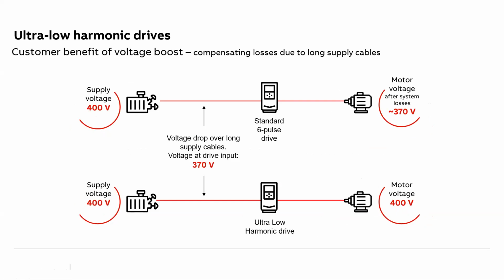Plus, there's a voltage boost functionality. This again is very important in places where large cable lengths are there. In many places, because of large cable length, there is a voltage drop. Plus, in some places there's continuous fluctuation in voltage. Because of this active component being inbuilt, it can compensate for this voltage drop and boost the voltage. So although the input voltage might vary, we can get the full desired output voltage. For example, if there's a long cable length or voltage fluctuation, and at the input of the VFD we are getting say 370 volts, the output would also be approximately 370 volts. However, in the case of an ultra low harmonic drive, even at 370 volts, we can get the full output voltage of 400 volts. This is possible with active front end technology.